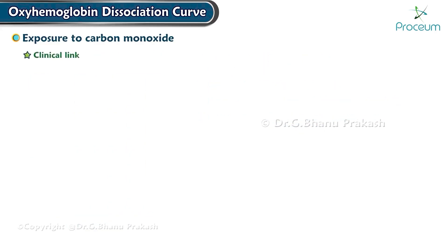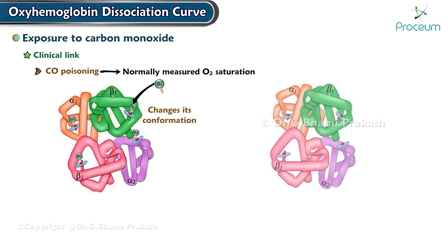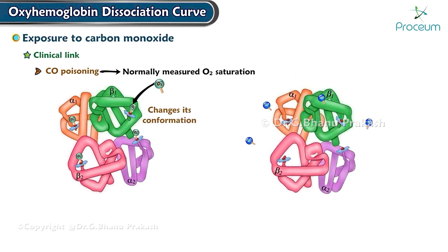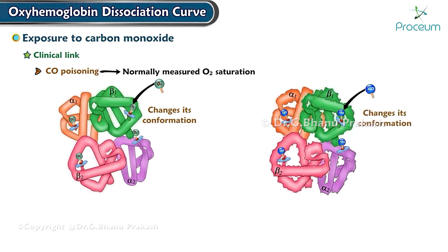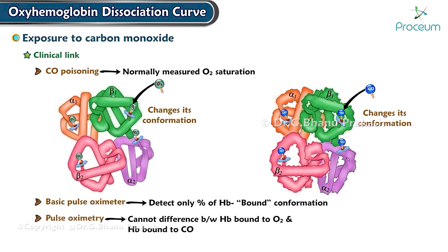Most individuals with carbon monoxide poisoning will have a normally measured oxygen saturation. The binding of oxygen to hemoglobin changes its conformation, and similarly, the binding of carbon monoxide to hemoglobin also changes its conformation. A basic pulse oximeter can detect only the percentage of hemoglobin that is in the bound conformation and cannot tell the difference between hemoglobin bound to oxygen and hemoglobin bound to carbon monoxide.